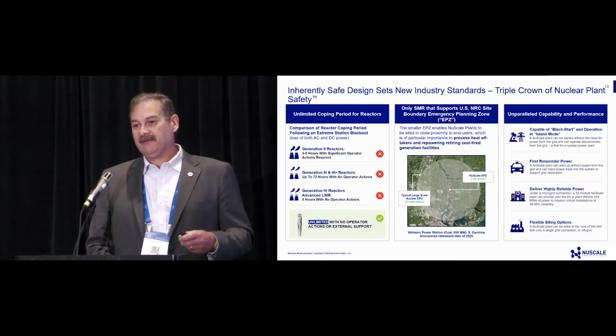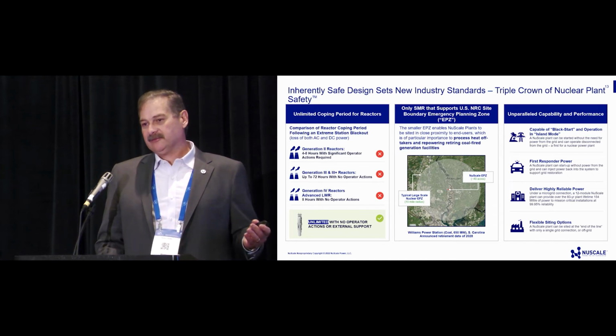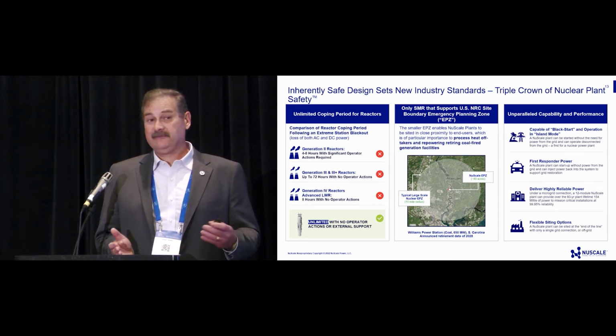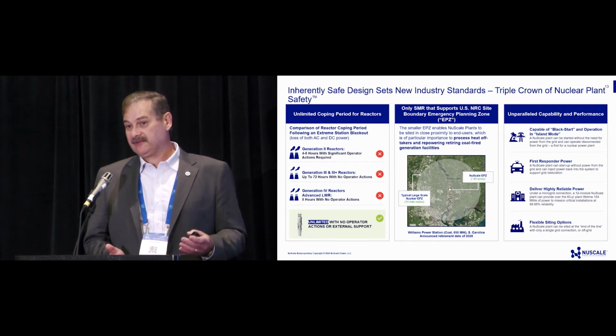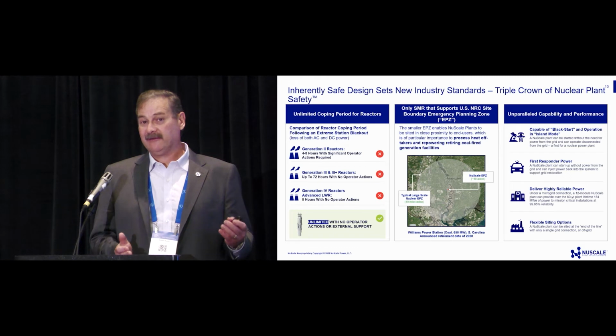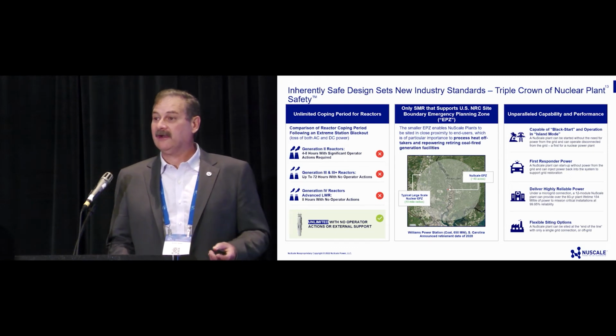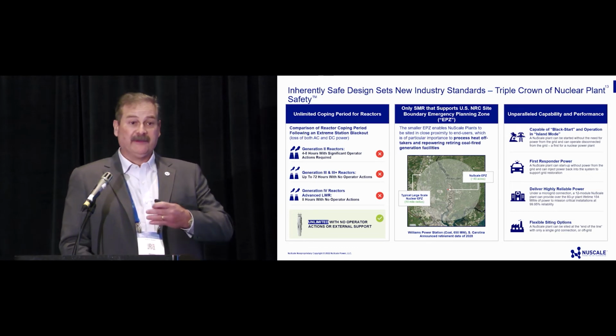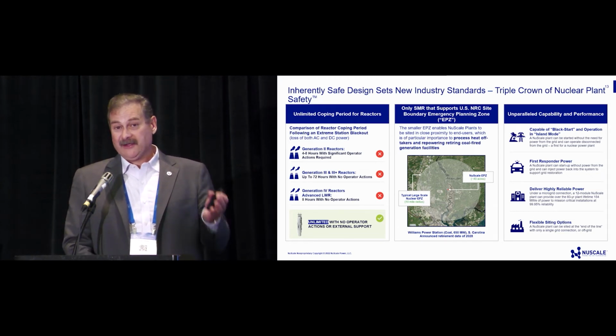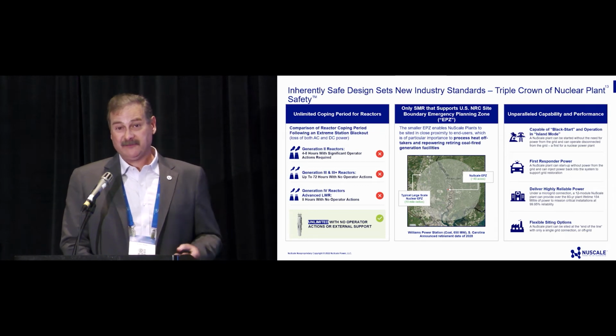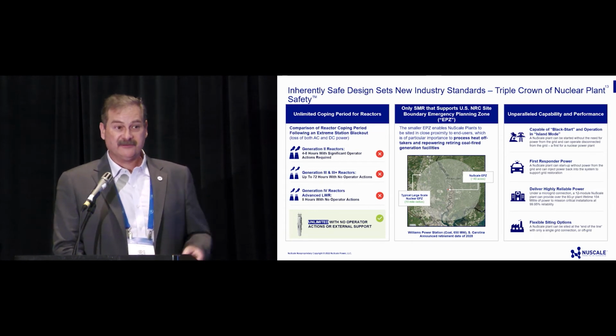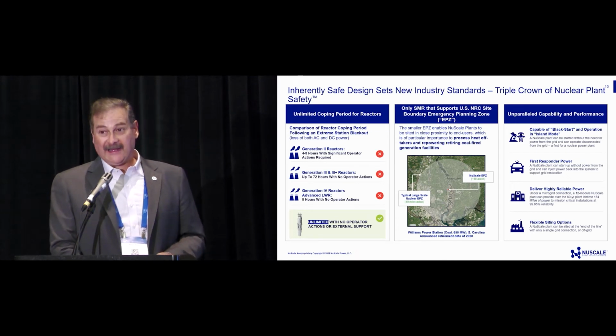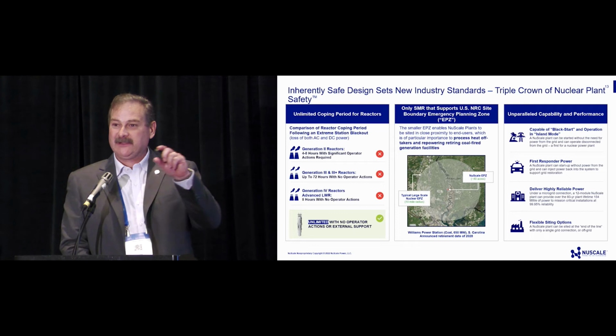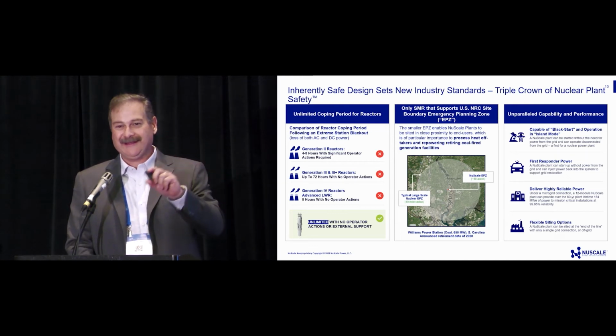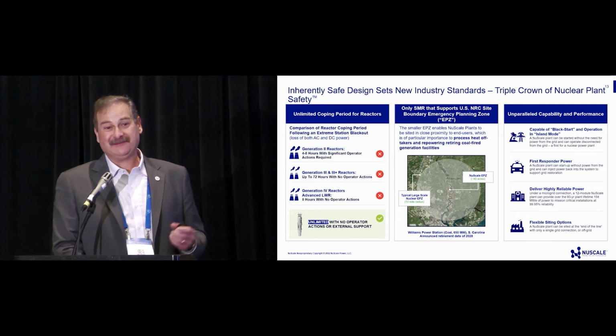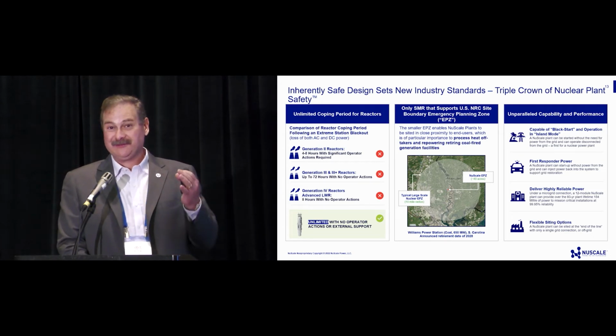Our systems, if we have a loss of a grid, all the modules trip their generators from their source, but all the steam gets 100% diverted and the reactors stay at 100% power, except for one unit that you would need to supply your house loads for your station. Then if there was an immediate return of power necessary, you already have your secondary system and your reactor running. You just have to ramp up the generator and sync it to the grid and start generating electricity. That's what we call the island mode. There's a picture of a palm tree in the simulator, which shows which unit is designated as the island mode unit when it's running, because it measures the health of the units and picks the healthiest unit to be the island mode unit.